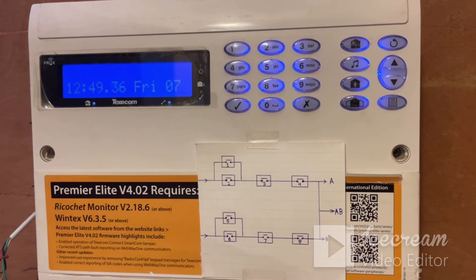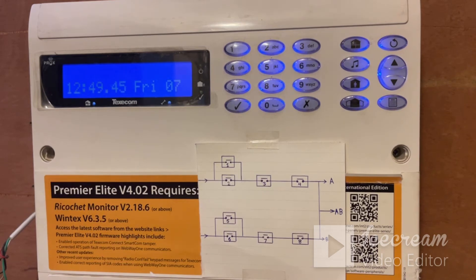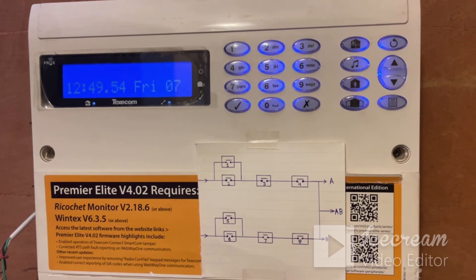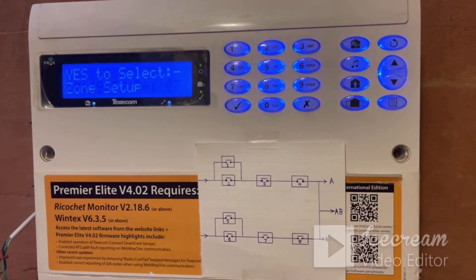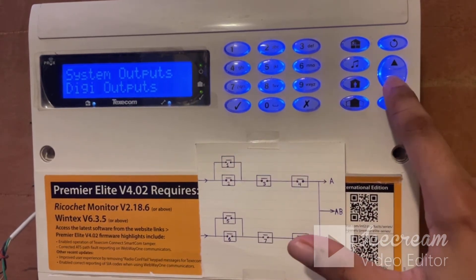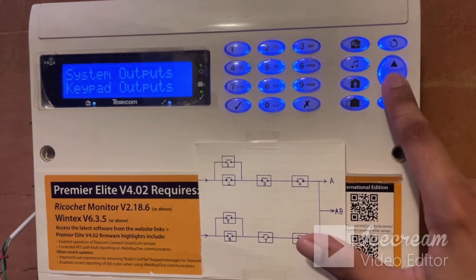Now, custom output stage A and B is not a physical output — it is a software output. We have to assign this software output to a physical output, which can be a DG output. For example, I want to define a logic where if my panel gets a guard alarm or a panic alarm, I want a particular DG output to activate. So there is an OR logic I want to use. We go to programming setup and press 6 to go to system outputs, then press yes.